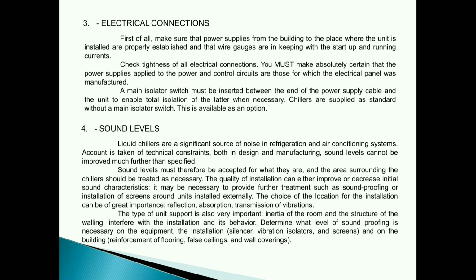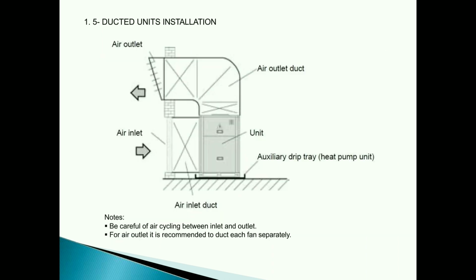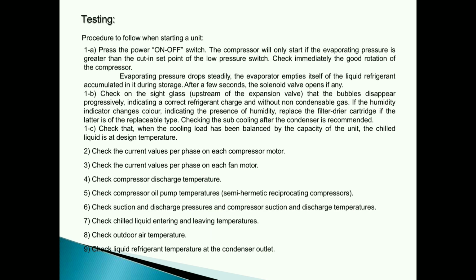Determine what level of soundproofing is necessary on the equipment, the installation, silencer, vibration isolators, and screens, and on the building, reinforcement of flooring, false ceilings, and wall coverings. 1.5 Ducted units installation. Notes: be careful of air cycling between inlet and outlet. For air outlet, it is recommended to duct each fan separately.